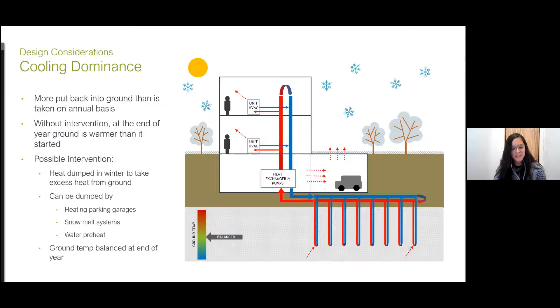Despite our cold winters, a lot of multi-unit residential buildings in Southern Ontario are actually cooling dominant. We've got these long cold winters and you'd think we'd be pushing heat out all the time, but because of these glass box multi-unit residential buildings you see a lot of, with high glazing ratios and not necessarily the best thermal performance of the wall assembly, we're actually in a situation with a lot of cooling dominant buildings. It just shows how much cladding design and building geometry can impact space conditioning demands.